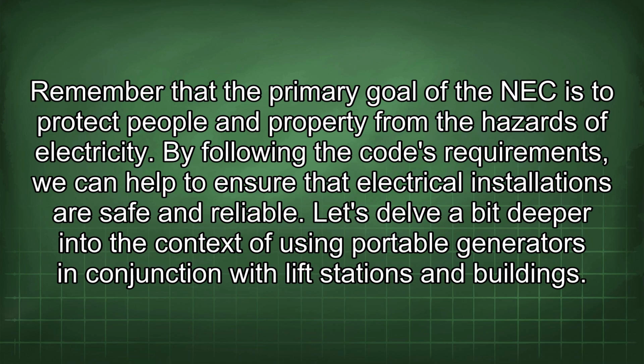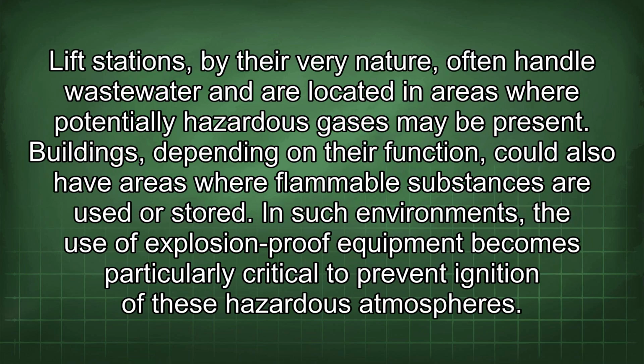Let's delve a bit deeper into the context of using portable generators in conjunction with lift stations and buildings. Lift stations, by their very nature, often handle wastewater and are located in areas where potentially hazardous gases may be present. Buildings, depending on their function, could also have areas where flammable substances are used or stored. In such environments, the use of explosion-proof equipment becomes particularly critical to prevent ignition of these hazardous atmospheres.